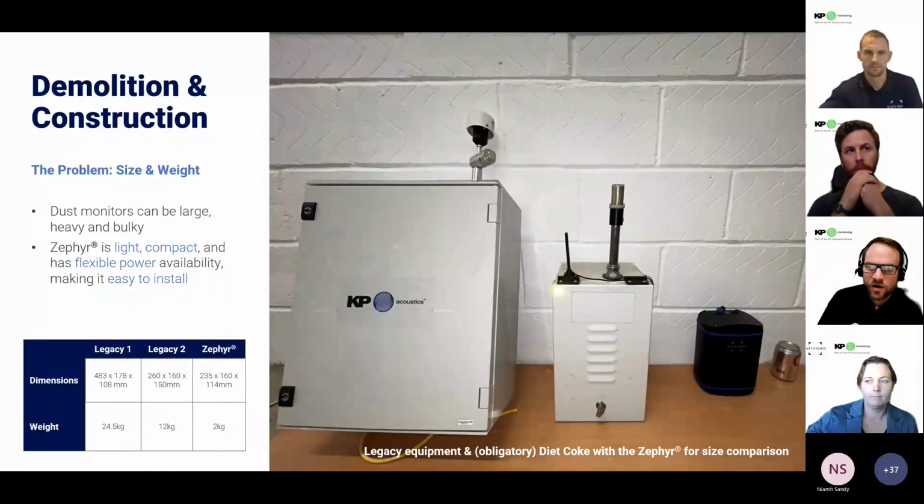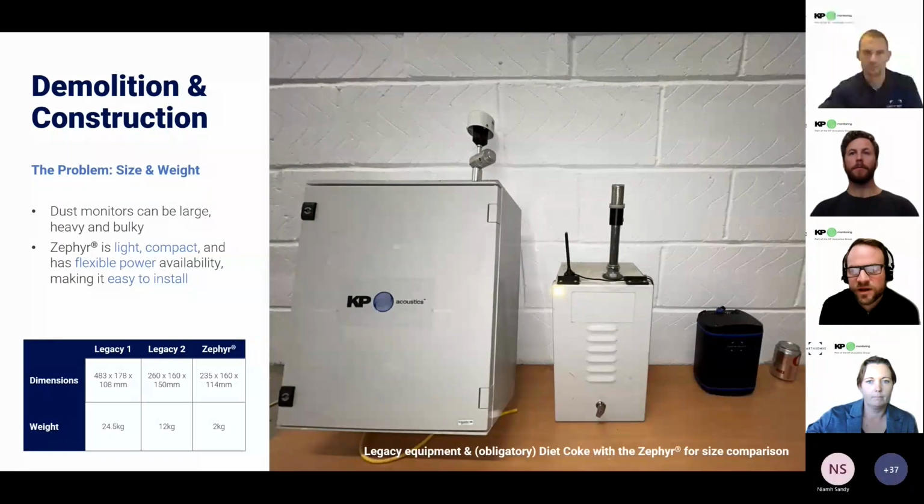Other units we have historically deployed tend to be large, bulky monitors, often contained within stainless steel cases, and in some cases, requiring 2 large separate enclosures to house both the sensor and the communication device. These devices also weigh around 12 kilograms, and that's before you include the weight of the enclosure, modems, and chimneys, and so on. They're difficult to lug around, and it requires no small skill to install them, particularly when you're trying to do that on your own.